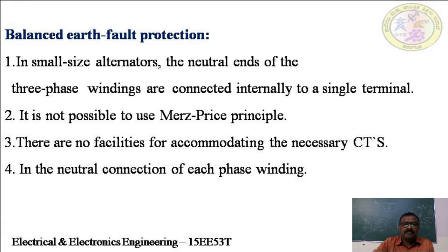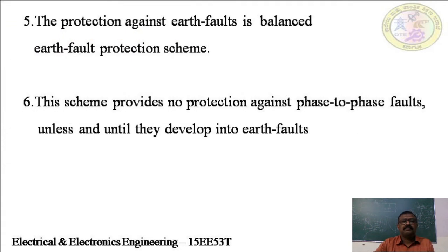Whenever connected in this manner, it is not possible to use the Merz-Price principle, where we have two CTs, CT1 and CT2, of 3 phase, connected to the equipotential points for the operating coil. There are no facilities for accommodating the necessary CTs in the neutral connection of each phase of winding. The protection against earth fault is the balanced earth fault protection scheme.